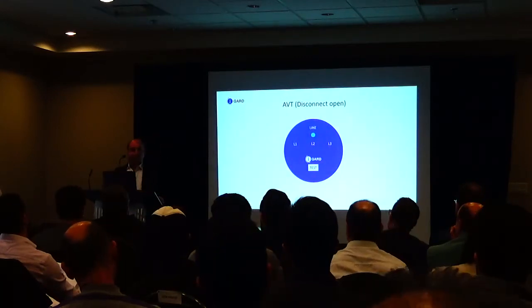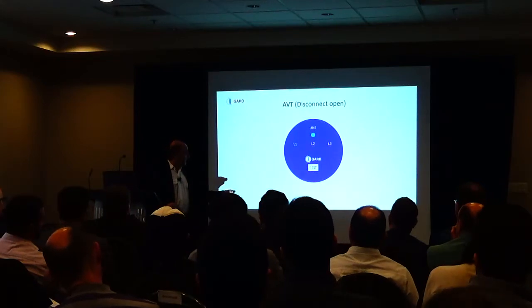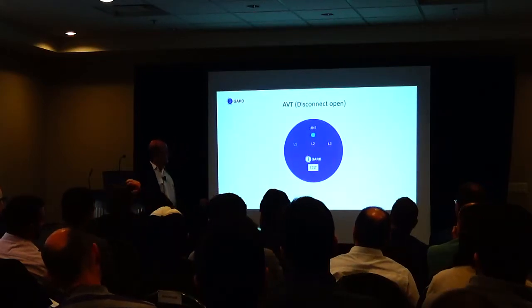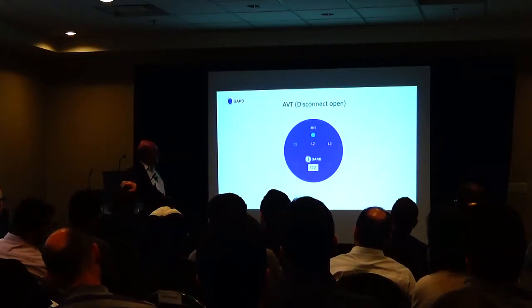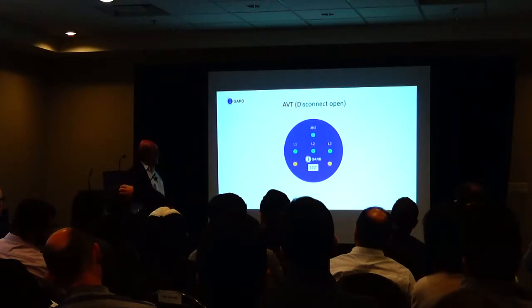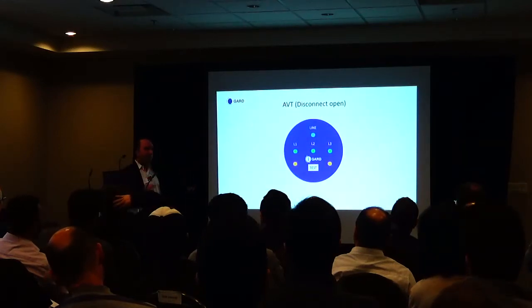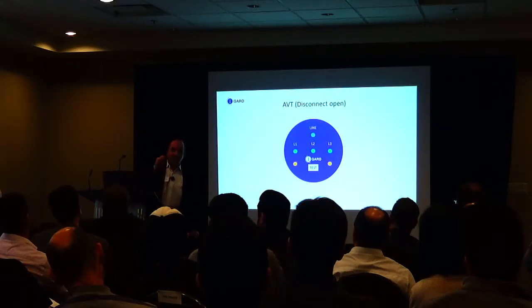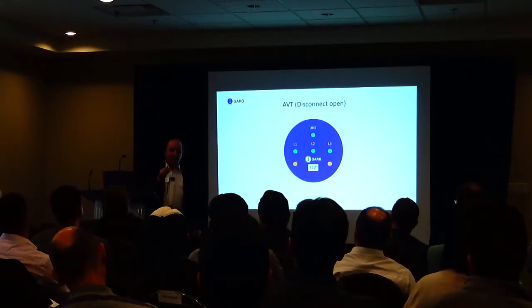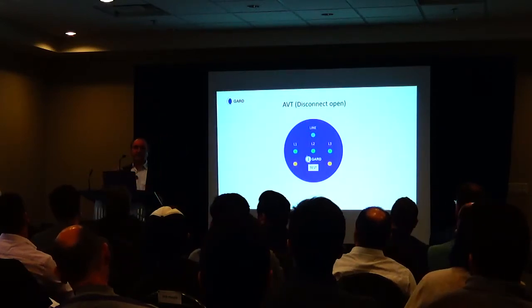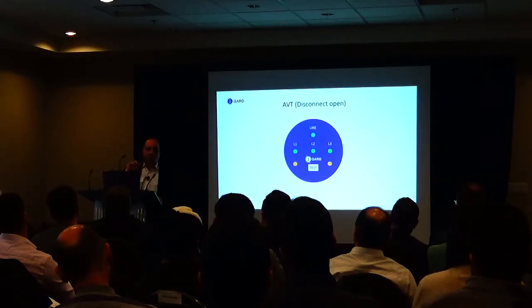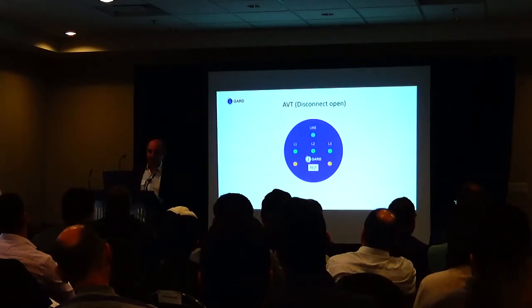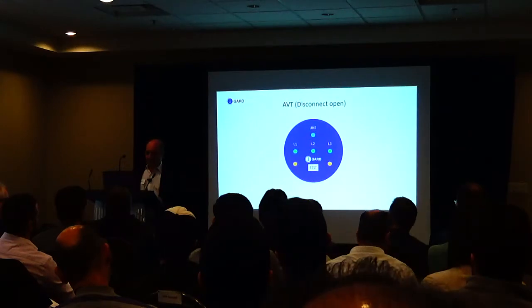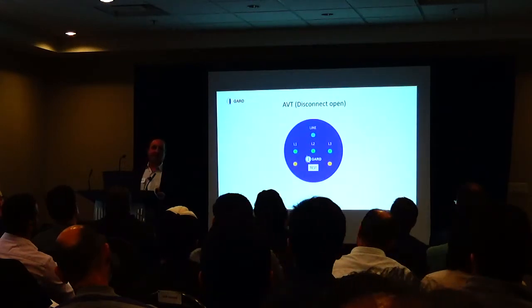So we test the push button. There's a test button right here. And we press the button, and it says I'm thinking. It's going to go out there and measure phase to phase, phase to ground. If it comes back with less than 3 volts, you get 3 green lights, meaning it is truly de-energized. So it has performed the test similar to the way Z462 says you have to perform the test. Now you can safely enter.